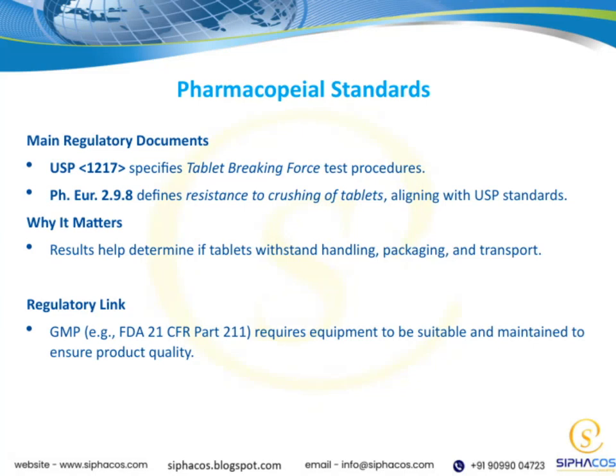Let's take a closer look at some of the key regulatory standards that guide tablet quality. USP 1217 specifies the procedures we use to test the breaking force of tablets, ensuring they can withstand handling. Similarly, the Ph. Eur. 2.9.8 standard defines the resistance to crushing of tablets, which aligns closely with USP standards. Why is this important? Well, the results from these tests help us determine whether tablets are robust enough to handle the stresses of handling, packaging, and transportation without breaking or losing integrity.